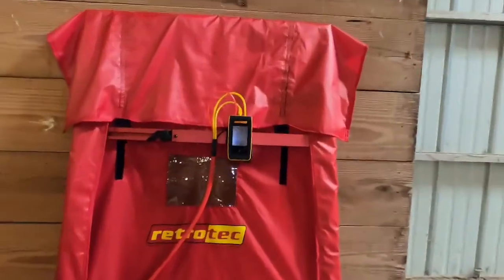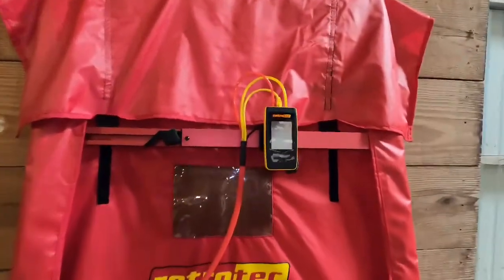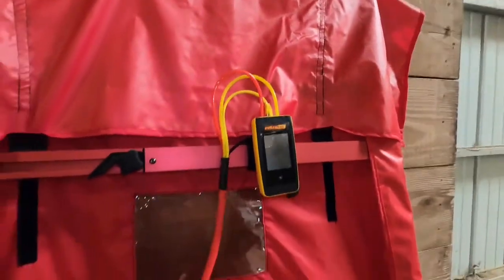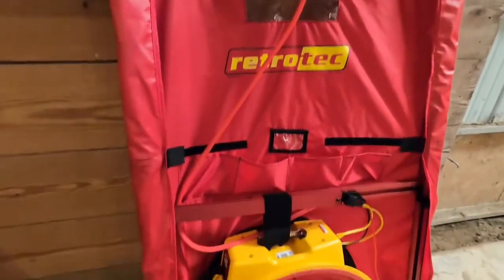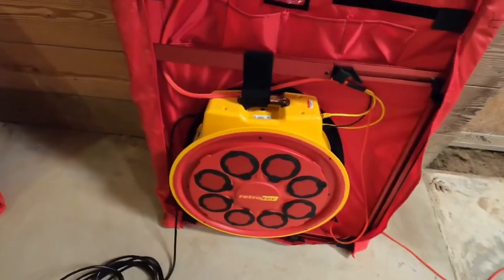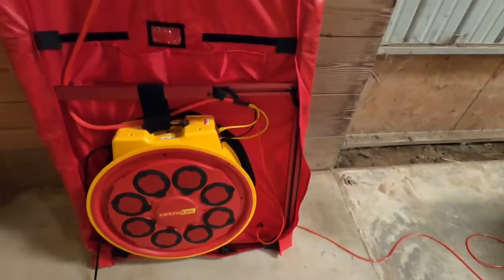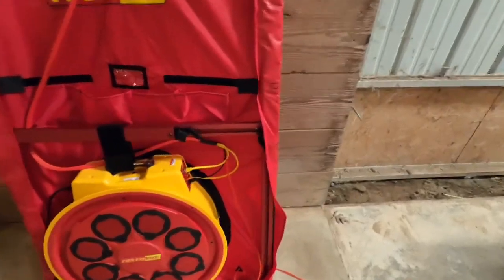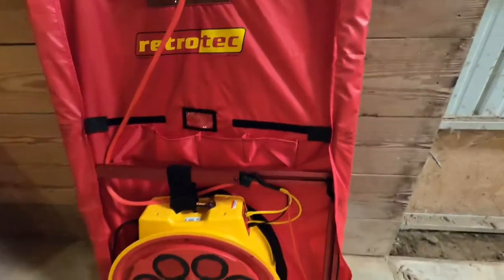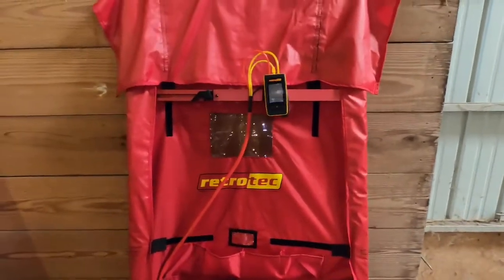Now we're going to talk about cord and cable management when your blower door is set up. Retrotec has come up with what they call the umbilical cord — it is a really slick way to manage all your hoses. It keeps everything super tidy and out of the way of the fan when it's running. The power cord comes off to the side here. There's no chance of any of this stuff getting sucked into the fan. Everything's really well thought out — I think that's a really slick system.